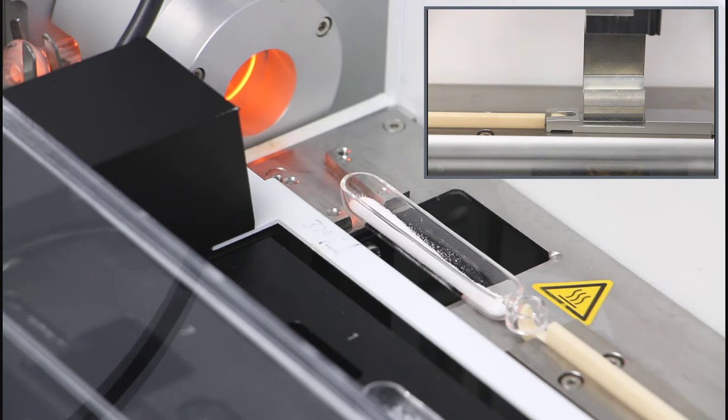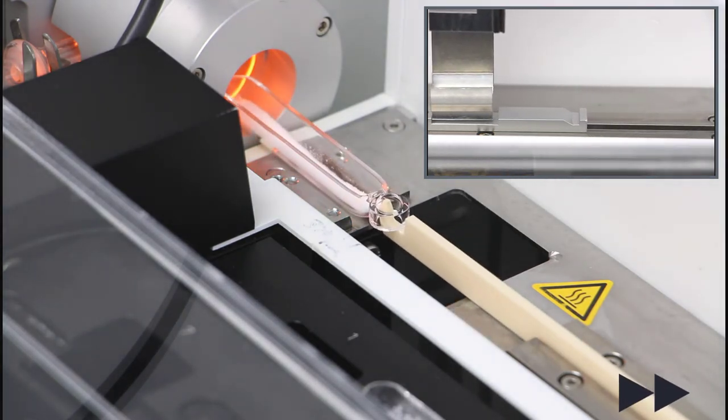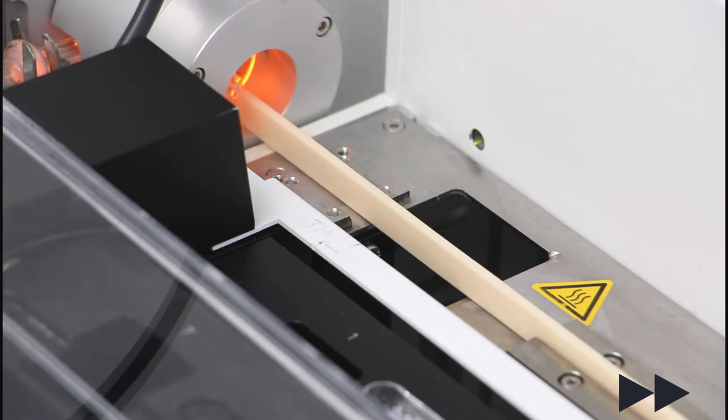The open-tube design is especially beneficial, since no mechanical parts are in the gas way and the gas lock is maintenance-free. Speed and holding positions can be programmed to the need of the application.